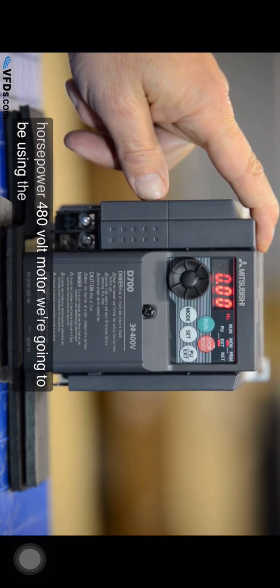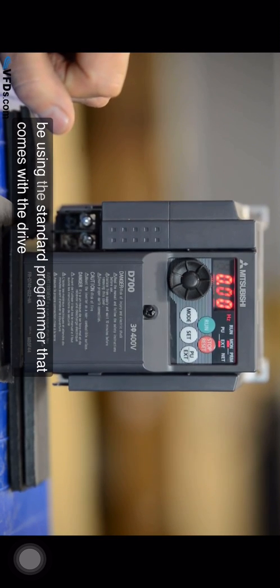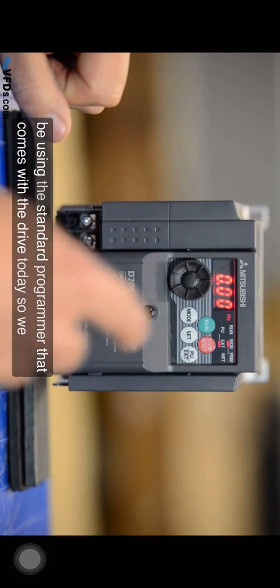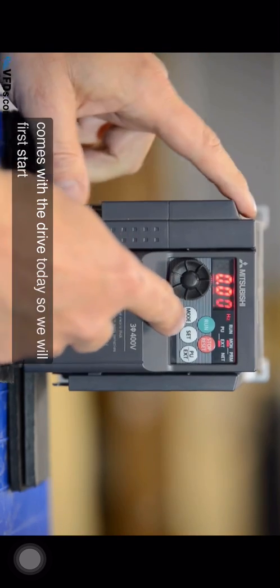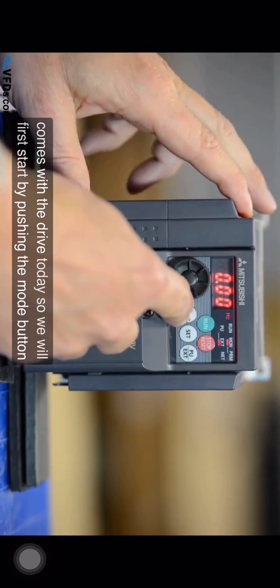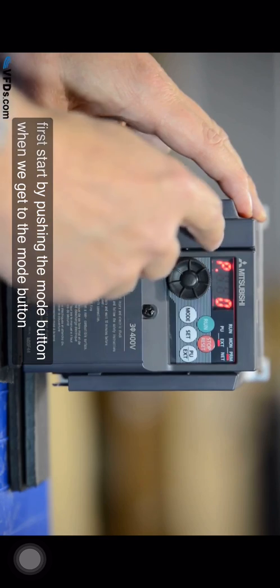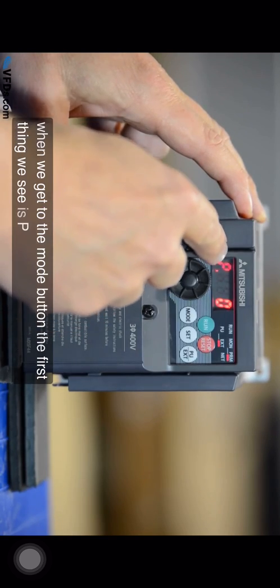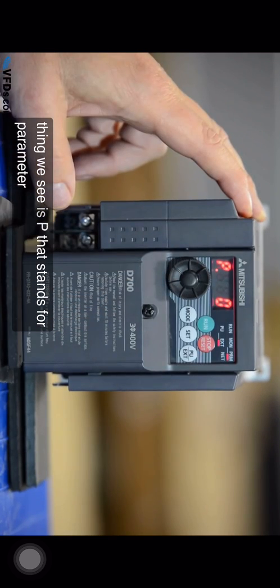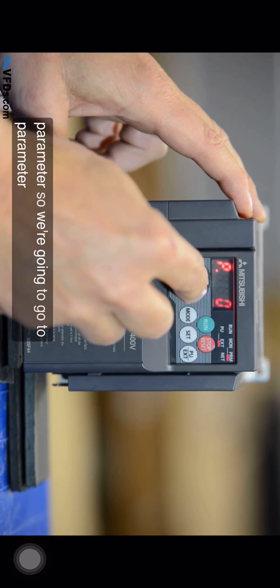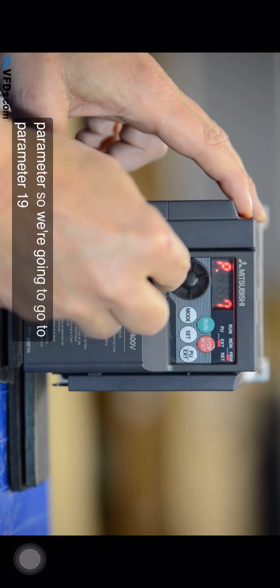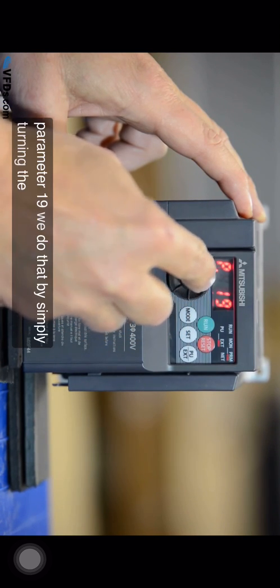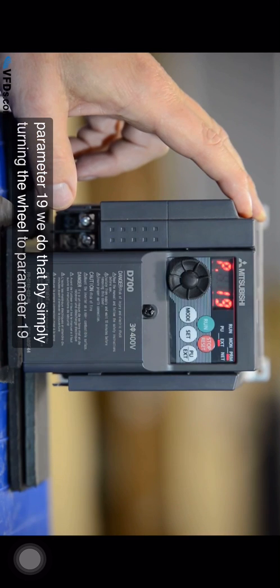We're going to be using the standard programmer that comes with the drive today, so we will first start by pushing the mode button. When we get to the mode button the first thing we see is P, that stands for parameter. So we're going to go to parameter 19. We do that by simply turning the wheel to parameter 19.